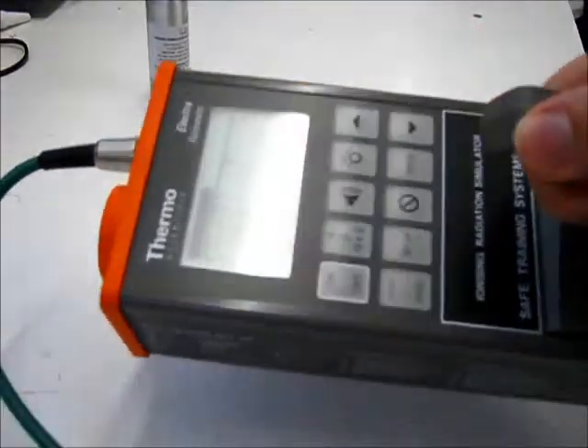What you can see now is that the probe has started to work, and on the instrument we now have a background reading which at the moment is showing approximately 2 counts per second. This reading is integrated into the instrument and is a randomly generated number, usually below 3 counts, but somewhere between 1 and 3 counts, just as a background figure.